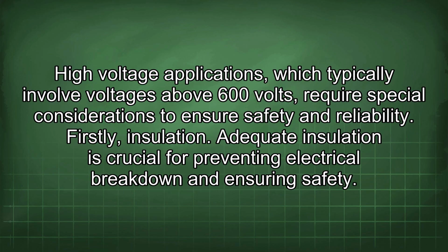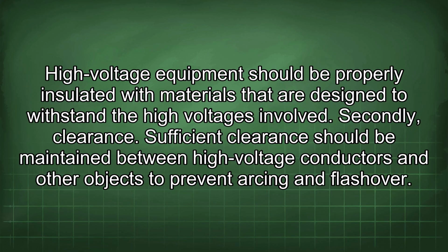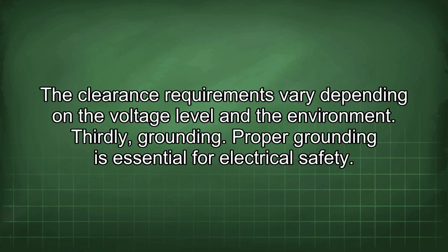High voltage applications, which typically involve voltages above 600 volts, require special considerations to ensure safety and reliability. Firstly, insulation. Adequate insulation is crucial for preventing electrical breakdown and ensuring safety. High voltage equipment should be properly insulated with materials that are designed to withstand the high voltages involved. Secondly, clearance. Sufficient clearance should be maintained between high-voltage conductors and other objects to prevent arcing and flashover. The clearance requirements vary depending on the voltage level and the environment.